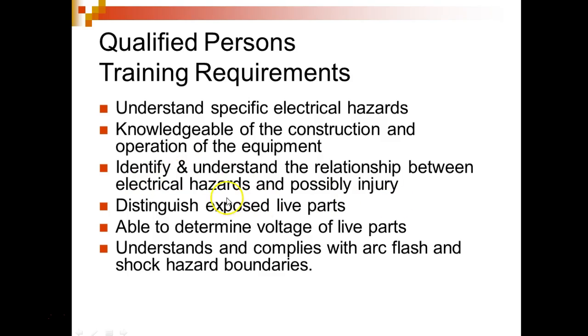Identify and understand the relationship between electrical hazards and possible injuries. Distinguish where the exposed parts are. Be able to determine the voltage of live parts. What that means is before you get into a piece of equipment, you need to know what voltages are available inside that equipment, right? Of course, we know what's available here. We've got 24 volts in the system, and we've got 120 volts at the power supplies. We'll go over there and look at the power supplies in a minute.